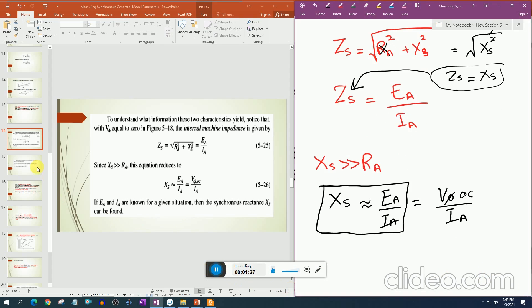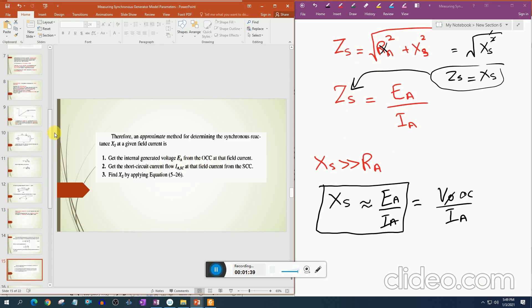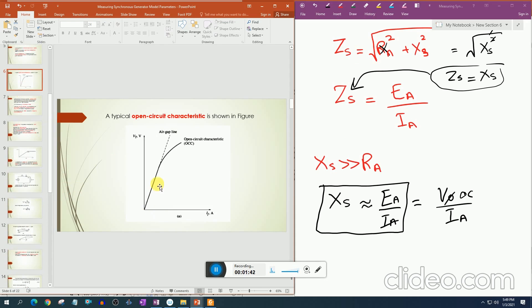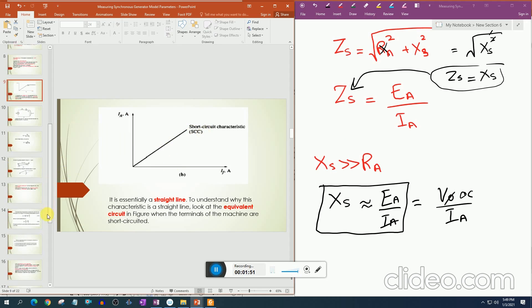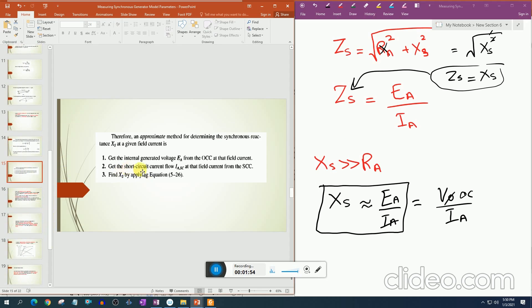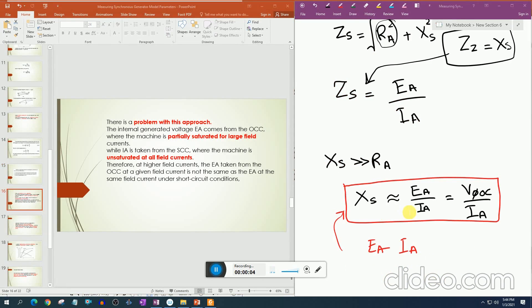This whole method can be generalized into three steps: First, get the internal generated voltage EA from the open circuit characteristics at a given field current. Second, at the same field current, find IA from the short circuit characteristics. Third, apply the formula Xs ≈ EA / IA to calculate the synchronous reactance at that operating point.